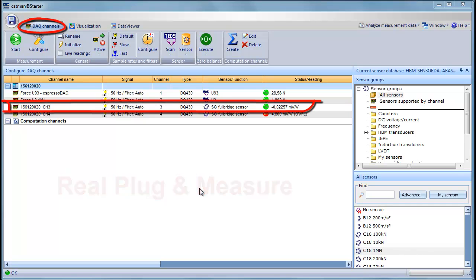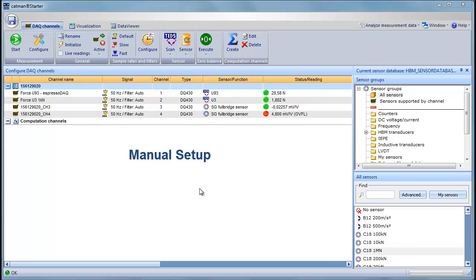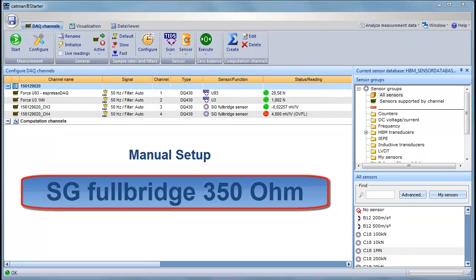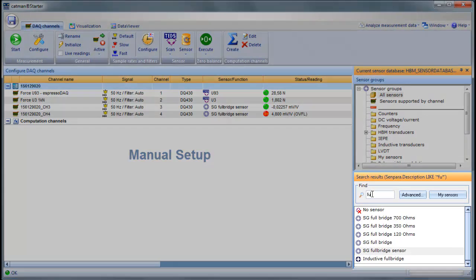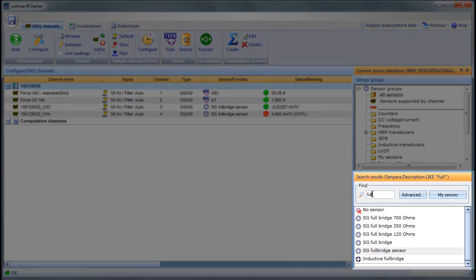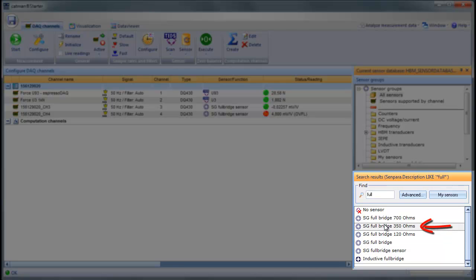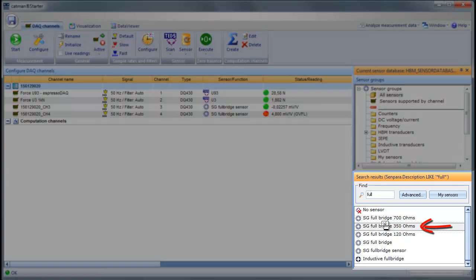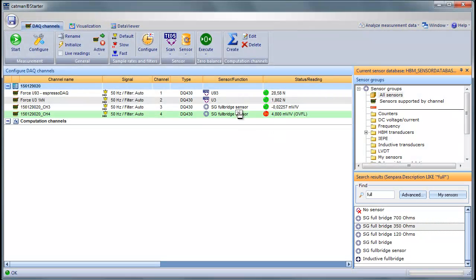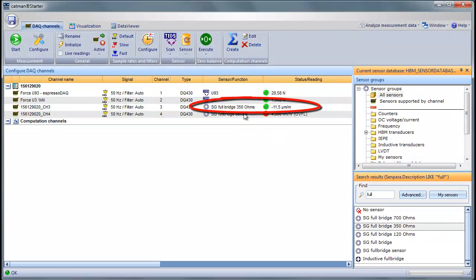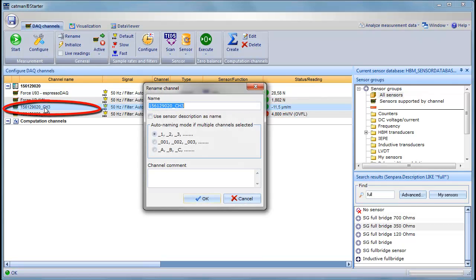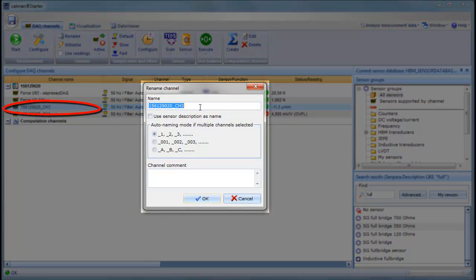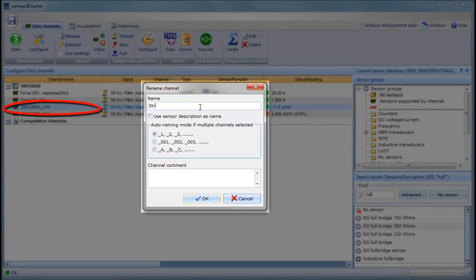Only channel 3, a strain gauge, requires manual setup. It's a full bridge with 350 ohm resistance. We'll search for it in the sensor database. There it is. We'll assign it to channel 3, and we're done. We should modify the channel name to make it something meaningful, so we'll name it Strain.